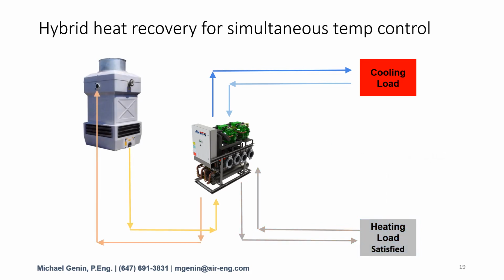Well, this could be done by switching over some hydronic piping, valves, and a heat exchanger. This chiller has the ability to be connected to both the heating load and a simultaneous auxiliary heat rejection device. It can automatically control to the hot water temperature and maintain the heating load by modulating how much heat is recovered between the two loads.